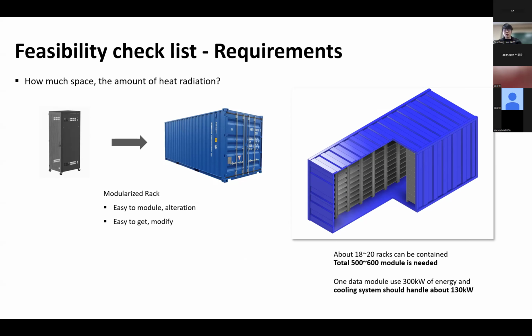About the size of a container, around 20 racks can be contained. If we target building a 10,000 rack data center, we'll need about 500 or 600 modules. Each module, the container-sized data module, uses 300 kilowatts of energy, so the cooling system will need about 130 kilowatts.